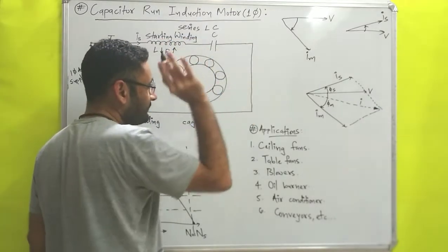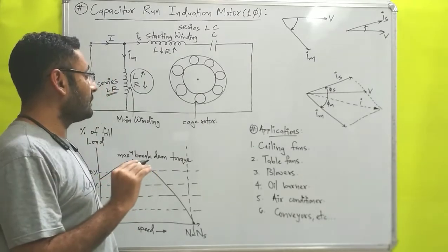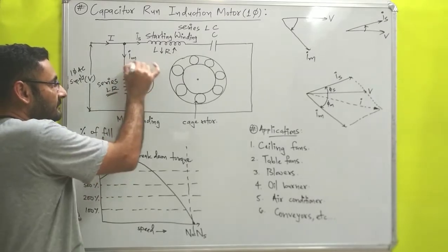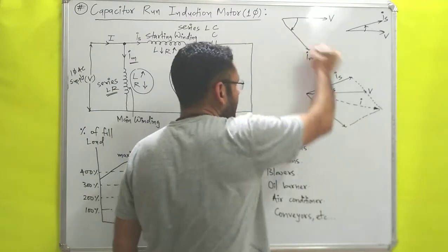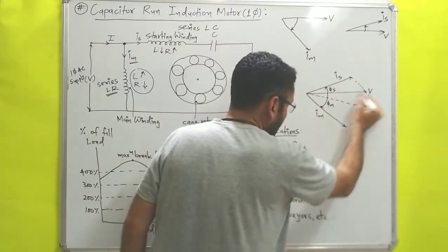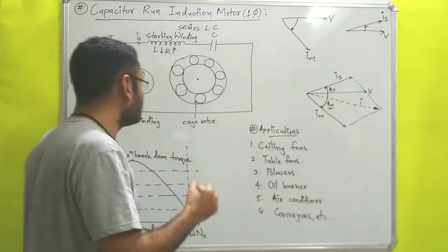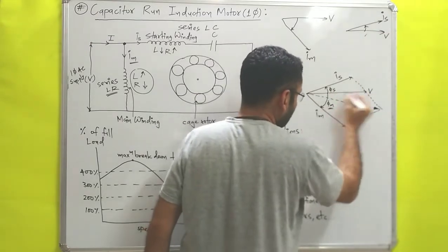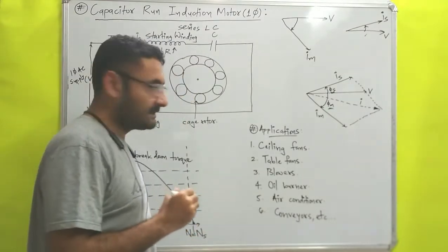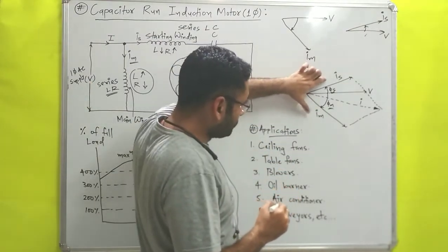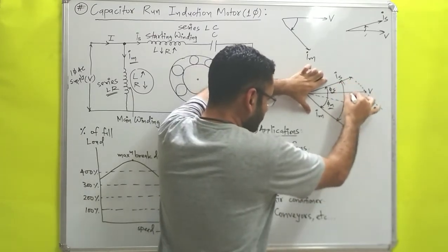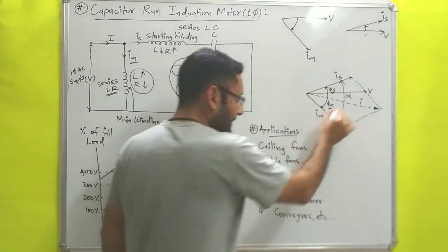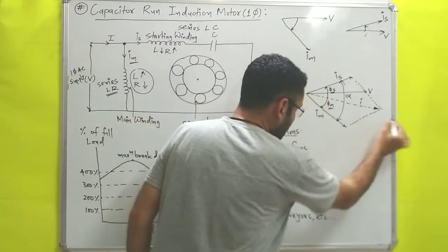Now for the working principle: the current Im flowing through the main winding lags behind the voltage by phase angle phi-m. The current Is flowing through the starting winding leads the voltage by phase angle phi-s. This means between both currents there is a phase difference, say alpha. To find the resultant current I, we draw a parallelogram of the two currents. According to Faraday's principle, the resultant current produces a magnetic field in a certain direction.